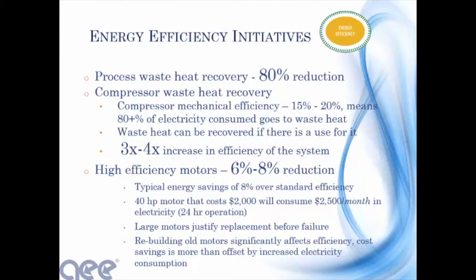If you're looking at new motors, you should definitely spend the additional few $100 to get the most efficient motor you can find. It used to be called NEMA Premium, which was beyond the standard efficiency. A few years back, NEMA Premium became the minimum standard, so all motors are now NEMA Premium. As soon as that NEMA Premium standard came out, the manufacturers started making what they call Super Premium, so they go beyond the NEMA Premium, and you can pick up a couple extra percent efficiency.